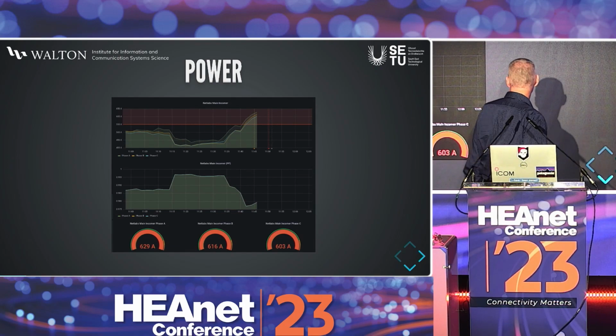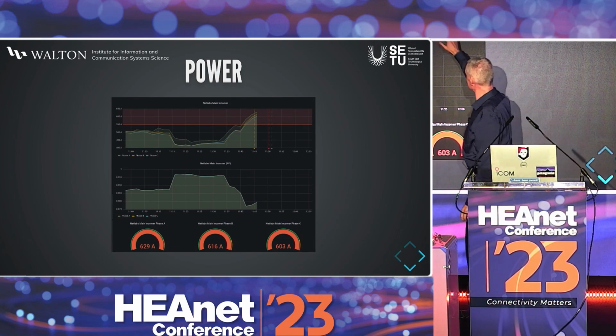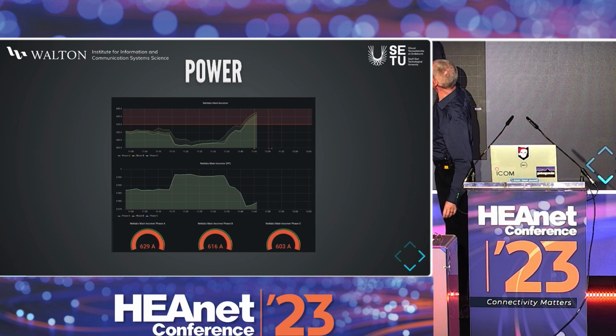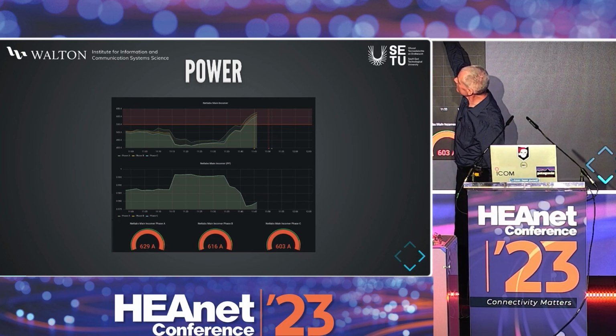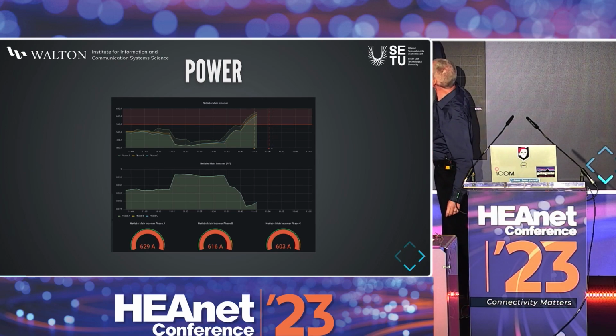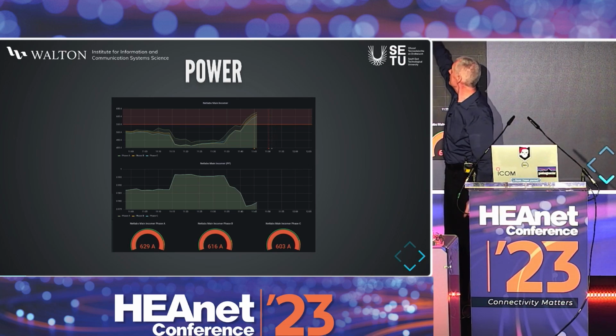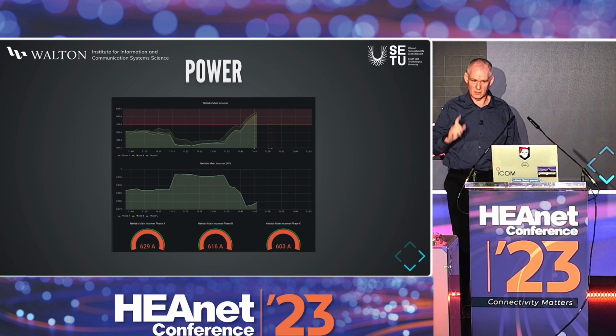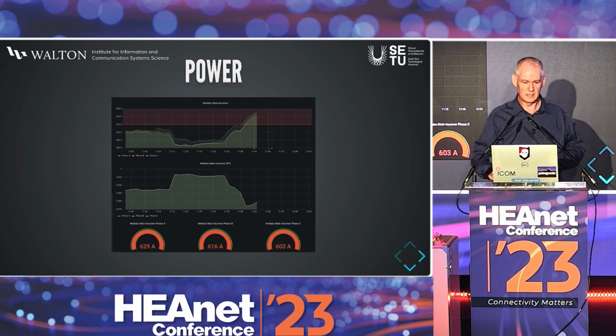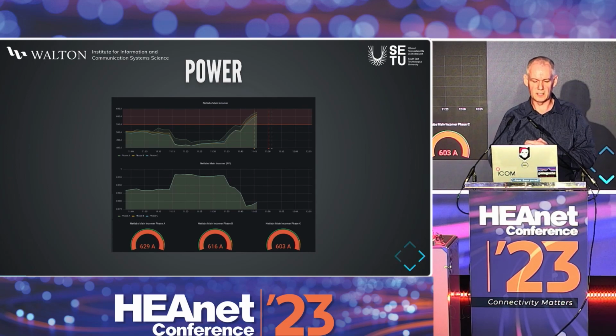So the interesting thing, because we'll come back to it, is that gap there. You can see we've gone over the red line, but basically 600 is the internal breaker of the building, and you can see we've gone above the 600 there. That's important, we'll come back to that later. The last values are 629 amps, 616, and 603. The breaker is set for 600.